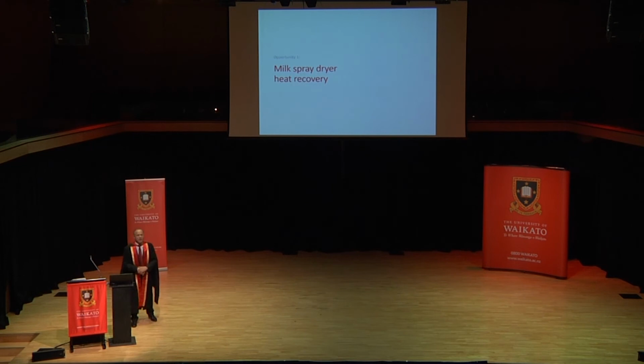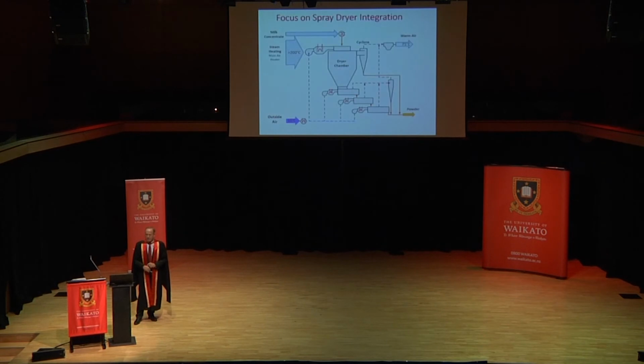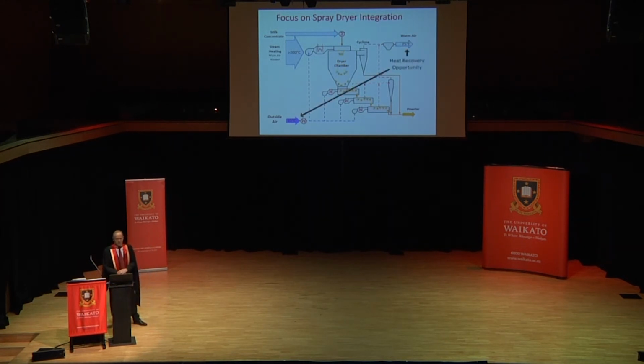So let's have a more detailed look at a milk spray dryer and how heat recovery can be achieved. Here's a schematic of a spray dryer operation. In the bottom left corner, outside air comes in at 15 degrees, is heated by steam to over 200 degrees, and mixed with milk concentrate at the top of the dryer. Evaporation occurs, milk powder is formed and comes out the bottom, and we end up with hot, warm air exhausting there.